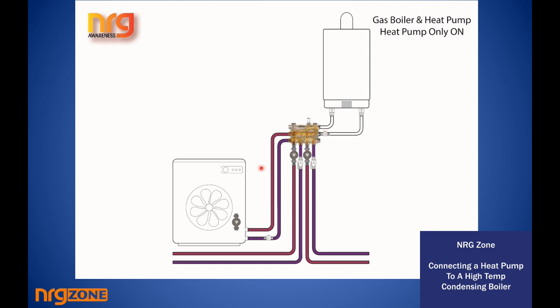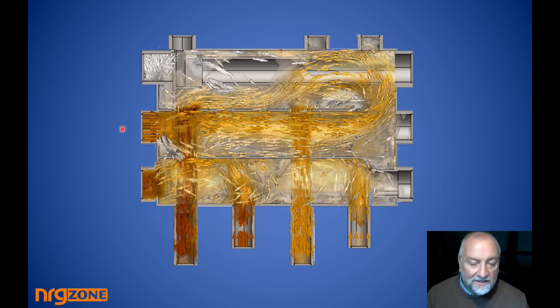There's something I want to say to you from the very start. The brown color you're looking at here is not temperature, it's density of flow. So if you have a high volume of flow, the program that did this interpretation of what's going on shows it to be a darker color, and the lighter color would show very, very little water activity, say up around here, because the water is being pulled up here from the heat pump, flowing in, flows straight across the bypass chamber, sucked up into here, taken down on the zones. This is taking less flow than that because obviously pump sizing or pipe sizing is different, and so this has taken the majority of the flow.